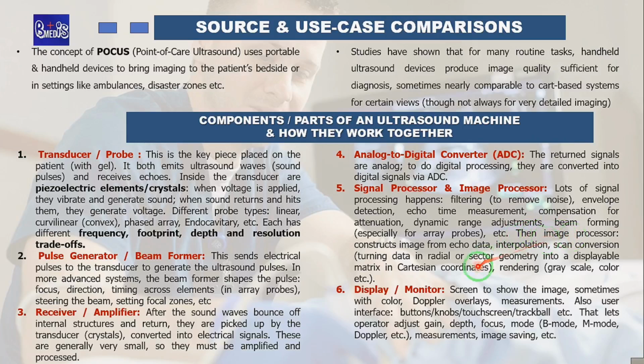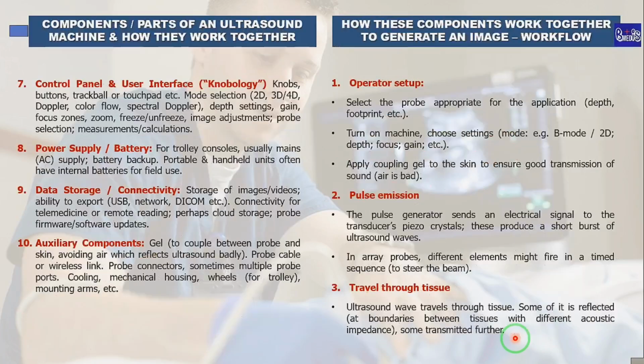Then the image processor constructs the image from echo data: interpolation, scan conversion, turning data in radial or sector geometry into a displayable matrix in Cartesian coordinates, rendering, grayscale, color, etc. Now we have the next component, which is the display or monitor. A screen to show the image, sometimes with color Doppler overlays, measurements. Also the user interface like the buttons, knobs, touch screen, trackball, etc. that lets the operator adjust gain, depth, focus, mode, B mode, M mode, Doppler, measurement, and image saving. So these are the components of an ultrasound machine.